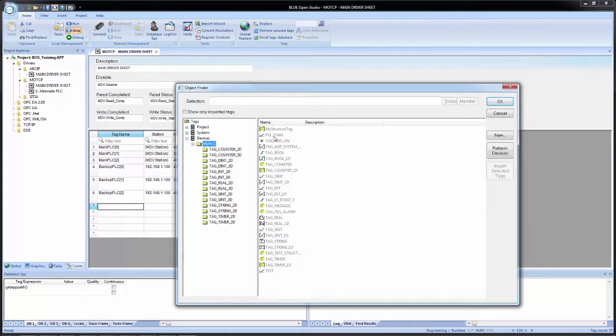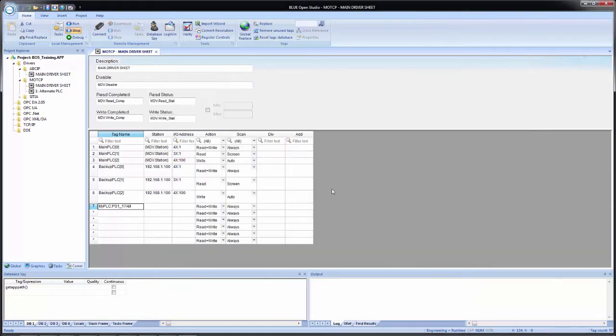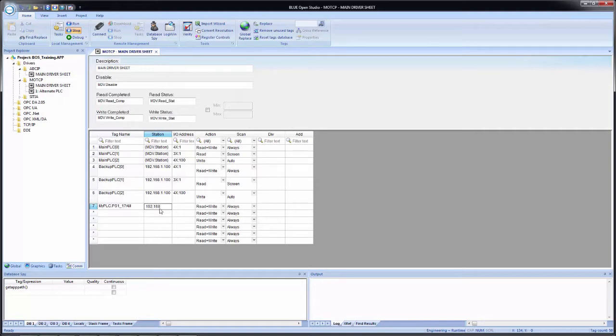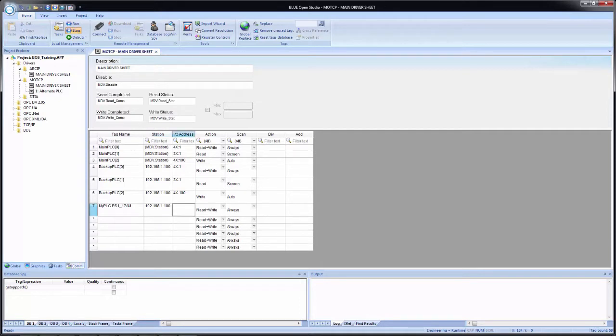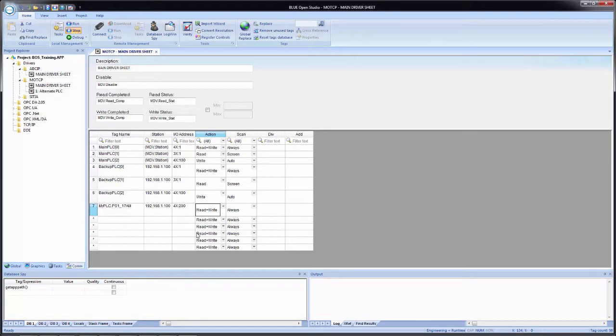So for example, I want to use this PS1 underscore 1748. I select it, click OK. I see it come in here. And now I simply would put in my station. In this case, 192, 168, 1, 100. And I want this to be a holding register of 4X, 200. And I want to leave it to a read and write and always.